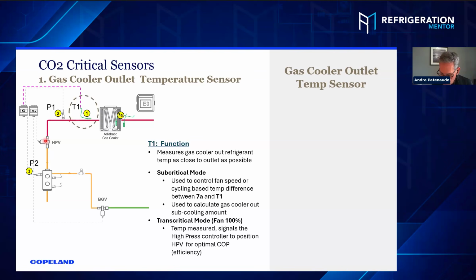Let me give an example. If T1 is measuring 60 degrees Fahrenheit, that's equivalent to 733 pounds saturation. So the controller will control this high pressure valve to maintain 785 pounds, which is 5 degrees higher than the actual temperature to throw it into a subcool range. That's dynamic. We're always trying to maintain 5 degrees subcooling, but it's moving up and down trying to do that. So that's one of its functions.